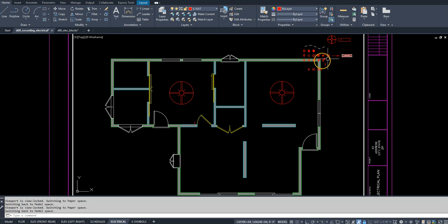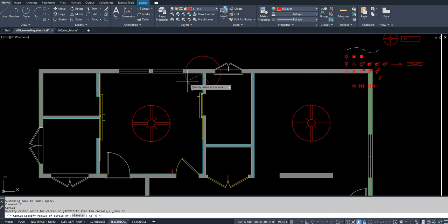In terms of the order in which you want to do things, it's your choice. Again, you've tried to plan this ahead by doing sketches. You should have an idea of how things should lay out based on what you have sketched. Based on our electrical code, we have to place a plug a maximum of 6 feet off of each corner.